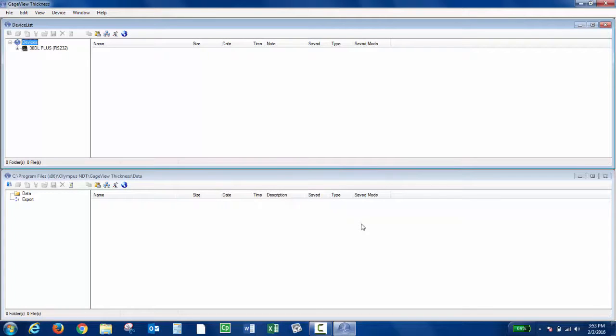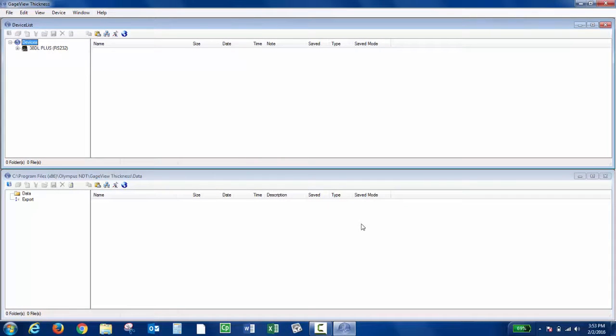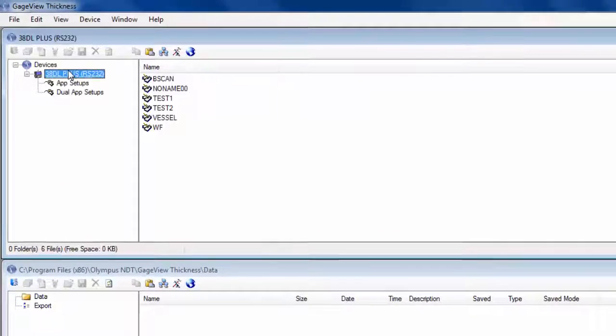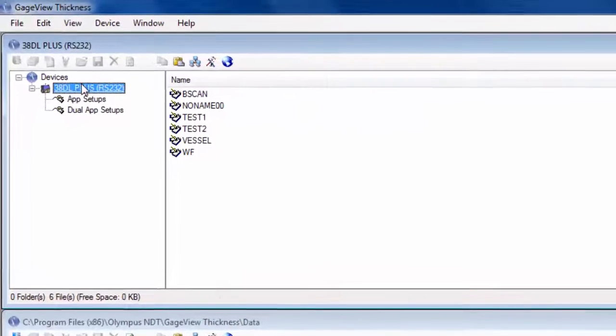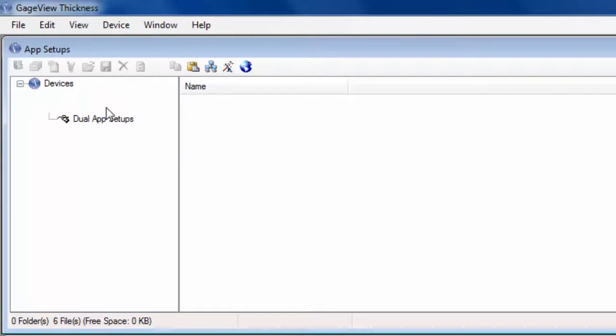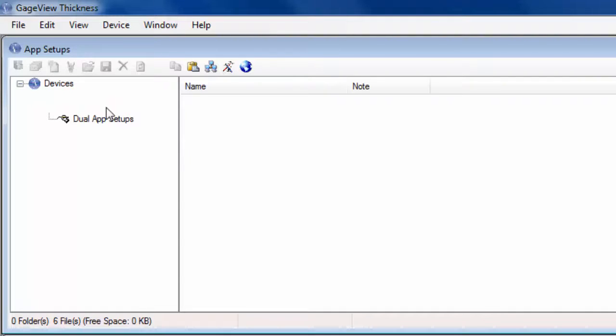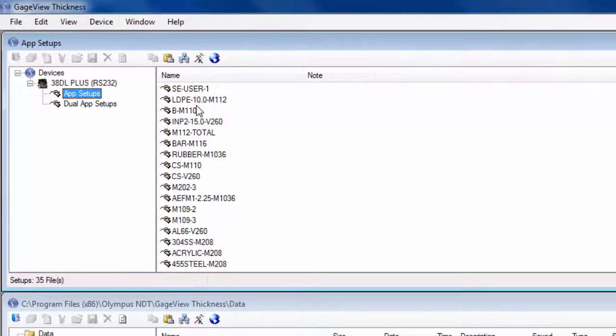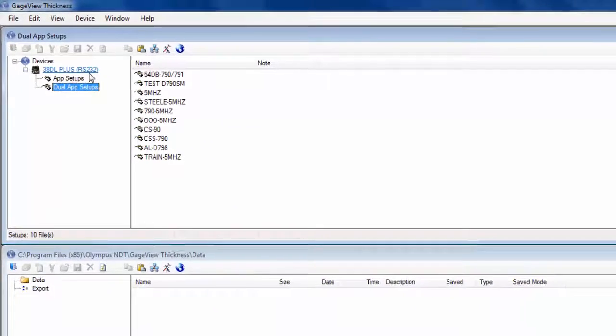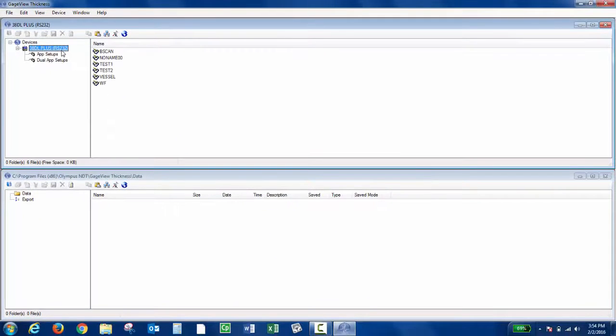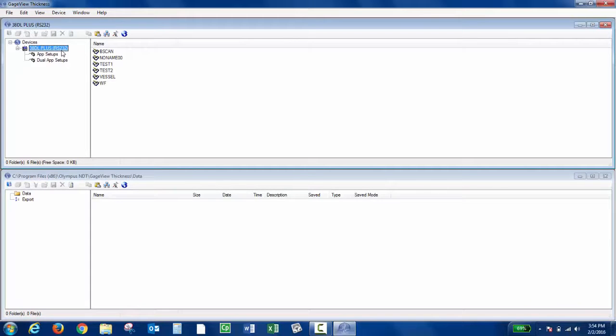The instrument should now be initialized and appear in the upper window under Devices. If I click 38DL Plus RS232, I'll see all the files on the instrument out to the right. If I click App Setups, I'll see all the Save Custom Single Element Transducer Setups. From here, now that the instrument's initialized, I can transfer the files to a database or export to Excel or CSV.